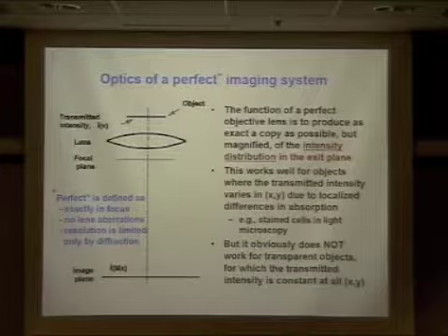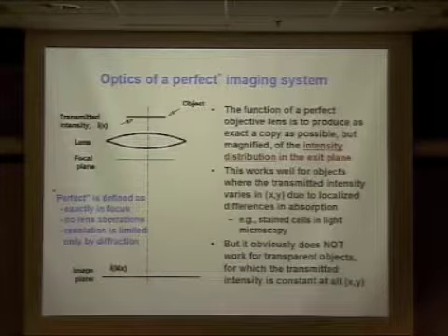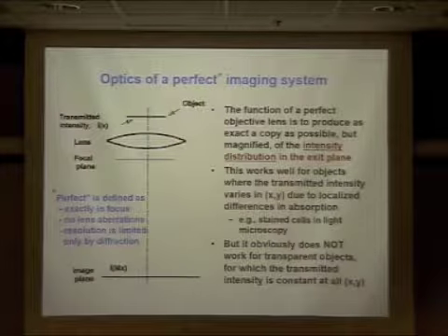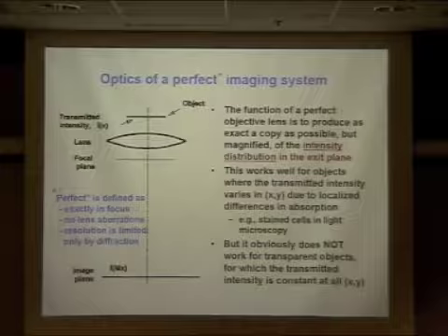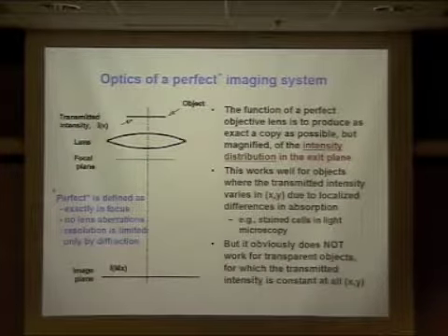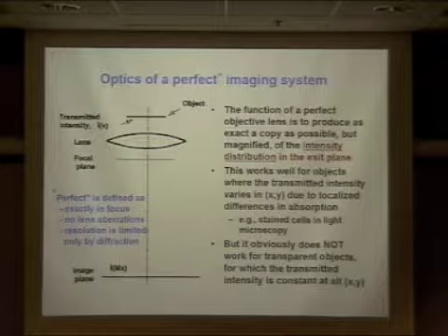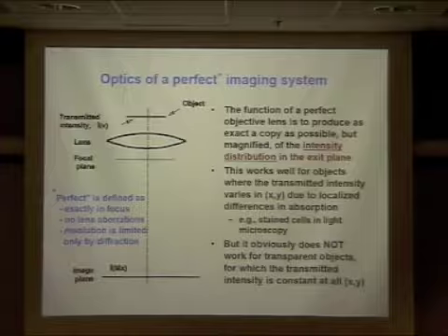That's called a diffraction limited image. And so the highest quality light optics are pretty much diffraction limited. Electron optics, we're not normally so fortunate, but the recent development of aberration correctors brings electron optics very close to the same goal of being diffraction limited.